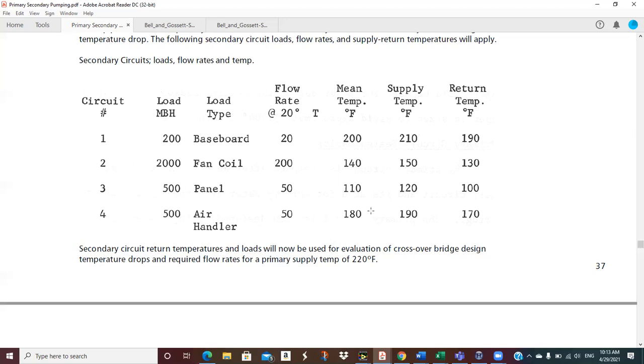Pretty simple math. Okay, circuit 2: I've got a bunch of fan coil units, and that's 2 million BTUs an hour. I've got a bunch of them strung up in that secondary. When I run the math on that, with a 20-degree delta T and 500, I get 200 GPM. So it's 10 times the first circuit, which makes sense. I'm going to spec these for 150-degree water in and 130 out, for a mean water temperature of 140.